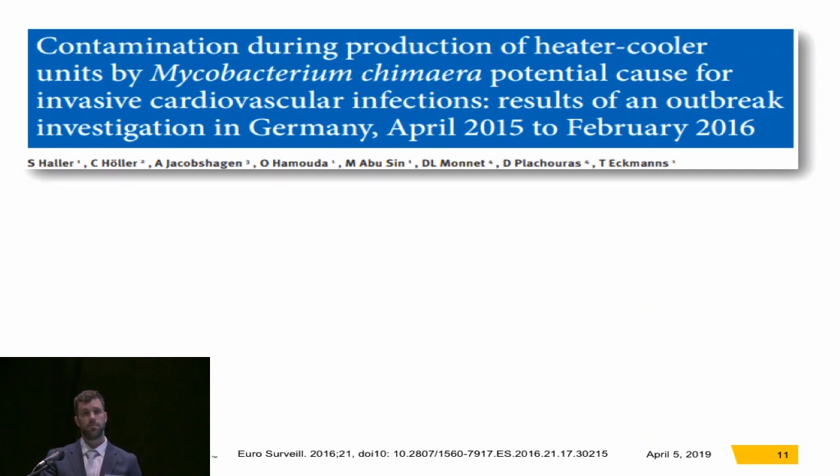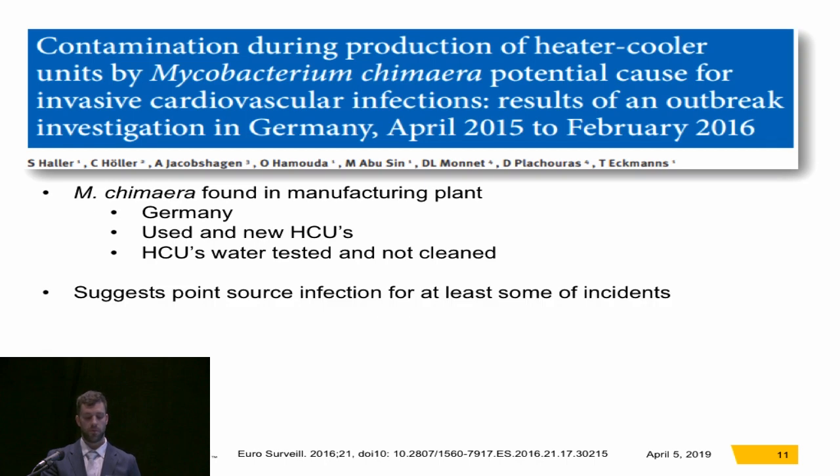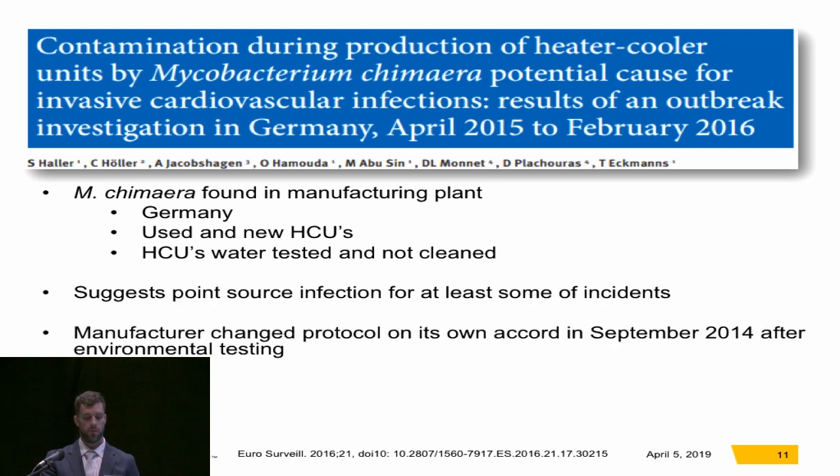After all these articles were coming out, Haller and colleagues began an investigation into what caused this global outbreak. What they found was that at the manufacturing plant in Germany, both used and new heater coolers all tested positive for M. chimaera. They found that the heater coolers were being water-tested and then not cleaned before being sent out to various institutions worldwide. This suggests that at least some of the infections had a point source origin. Notably, the manufacturer changed their cleaning protocol on its own accord in September 2014, after their own environmental testing found the infection risk.